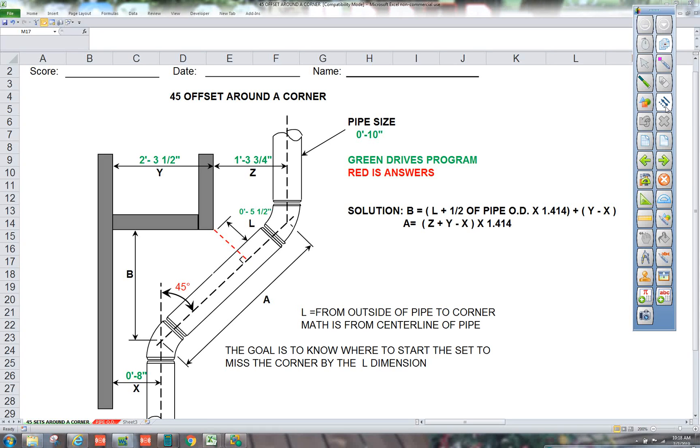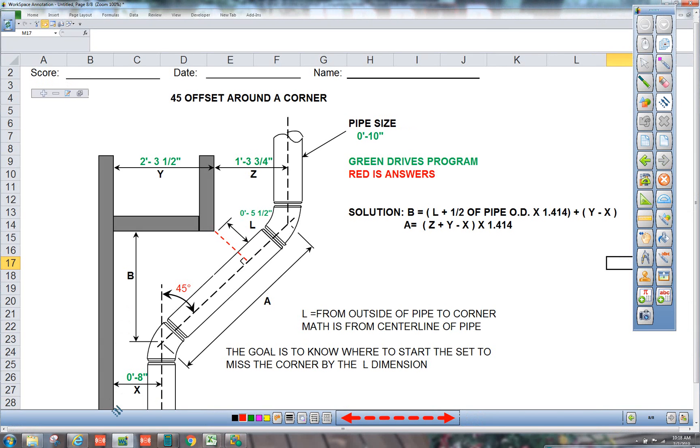we have what we call 45 offsets around the corner. And what we have here, we have the building structure, this wall, and many times we have to keep our pipe close to that to keep it out of the ceiling. And we have to maintain a desired dimension from that corner, and that would be L. That would be a perpendicular measurement, and we want to maintain L.